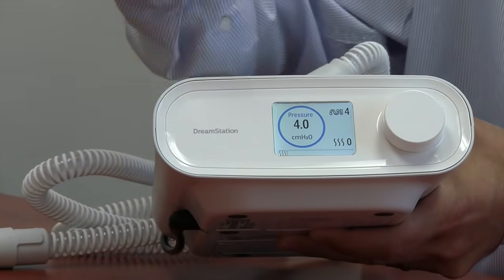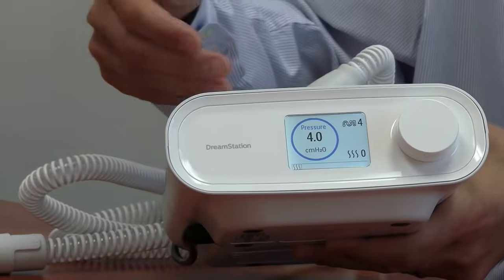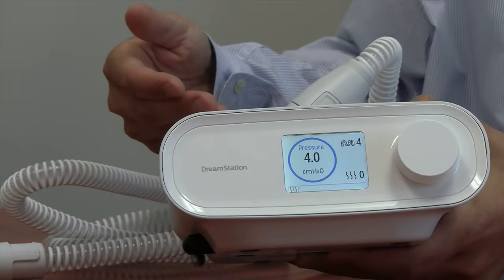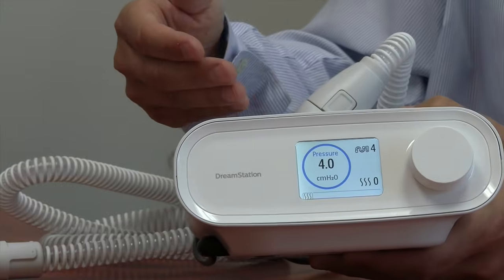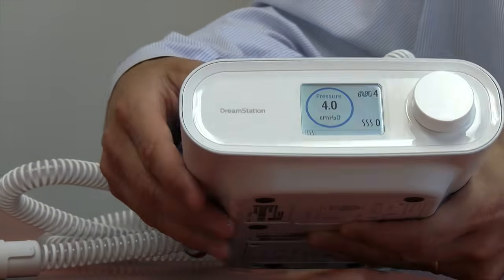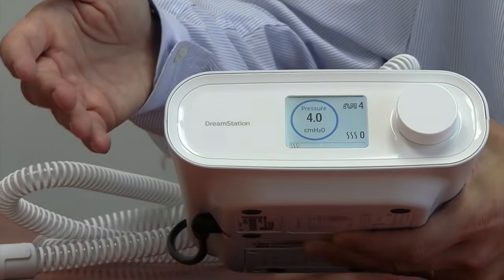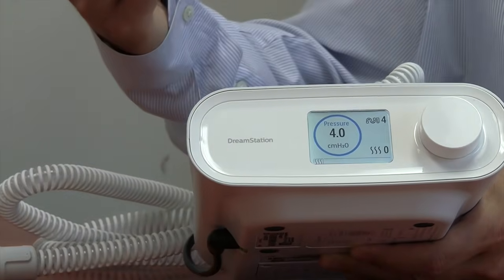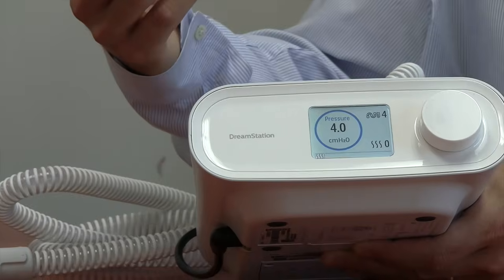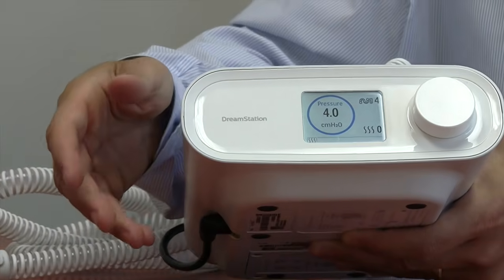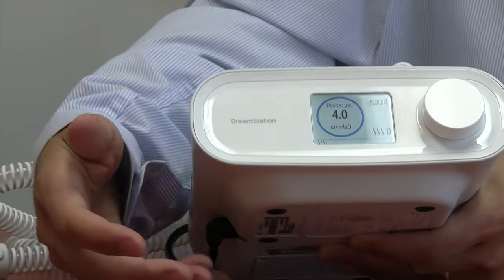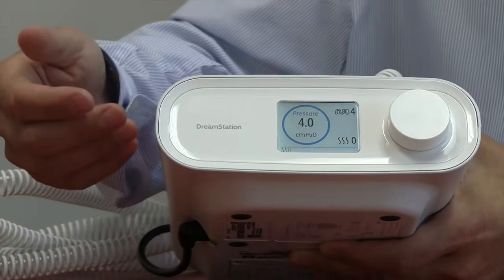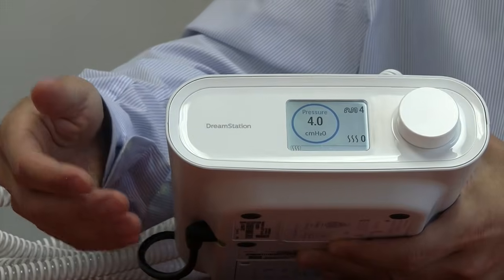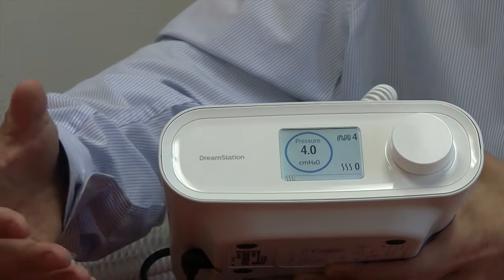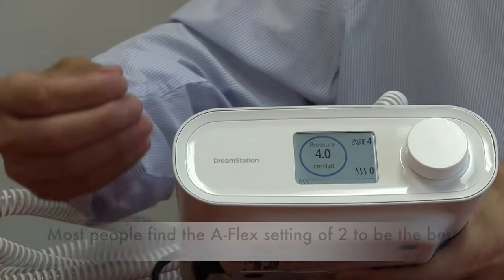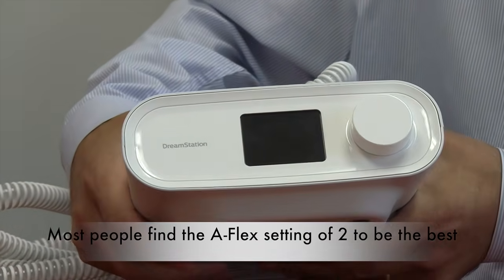It is on a pressure of 4, and this machine, like all their CPAP machines, can range in pressure from 4 to 20. And this does have the classic modes of A-Flex and C-Flex built into it also, which means it's going to drop pressure. So if this patient is currently sleeping, let's say they're on a pressure of 10. When they breathe in, it's giving a pressure of 10. If the A-Flex is enabled, it will drop the pressure just for a split second, so that it's more comfortable therapy. The person's breathing in, it's giving them a 10, and when they breathe out, maybe it drops the pressure all the way down to a 7 or an 8. That way they're not pushing out against such a high pressure, they're breathing out against a lower pressure. It makes the therapy much more comfortable.